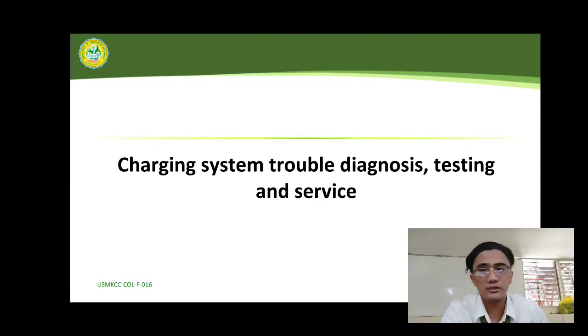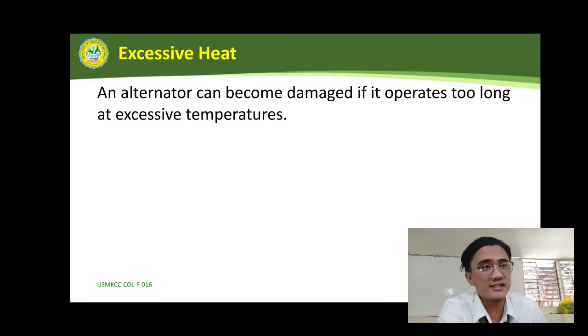First is excessive heat. An alternator can become damaged if it operates too long at excessive temperature. Damaging heat levels are generated in two ways: when the alternator becomes dirty, either externally or internally, restricting its ability to dissipate heat from its external surface or let air pass through the unit; and when the air ducts or heat shields are not replaced after the alternator has been serviced.